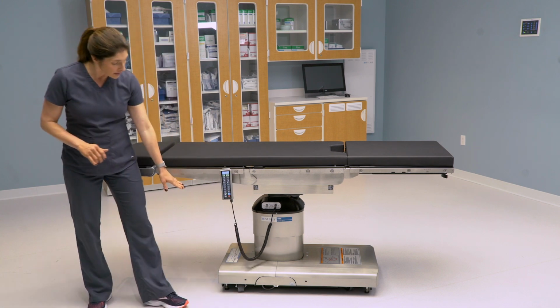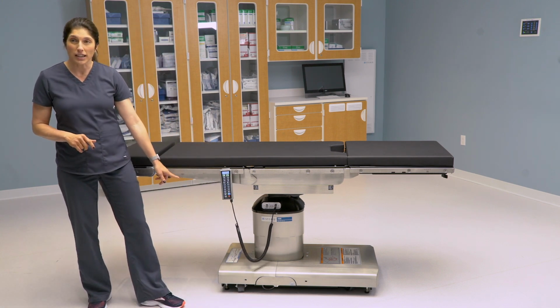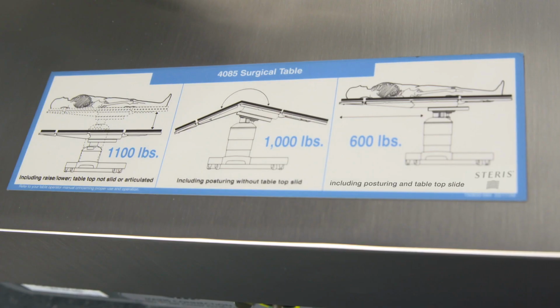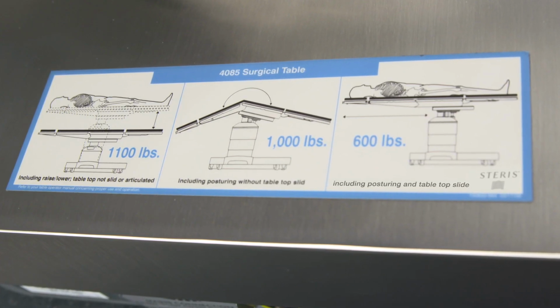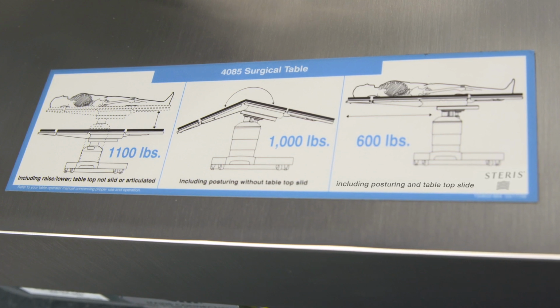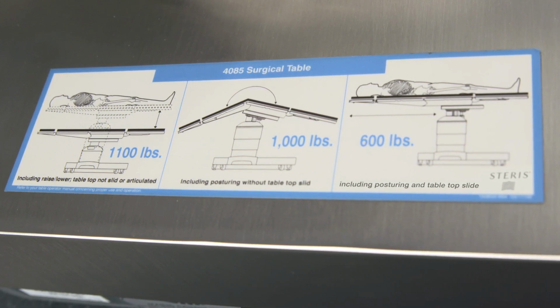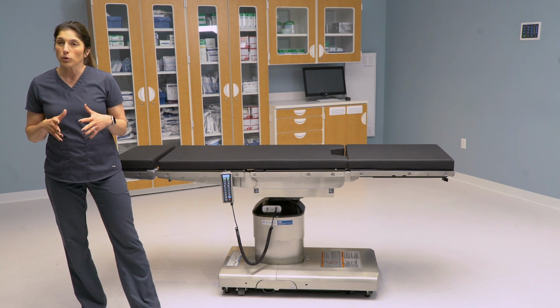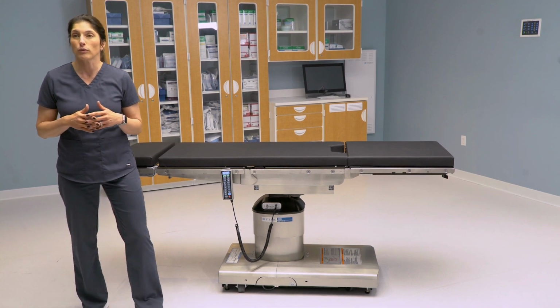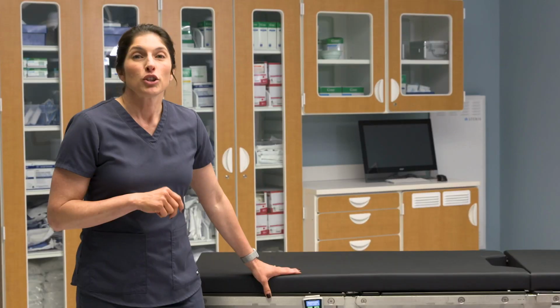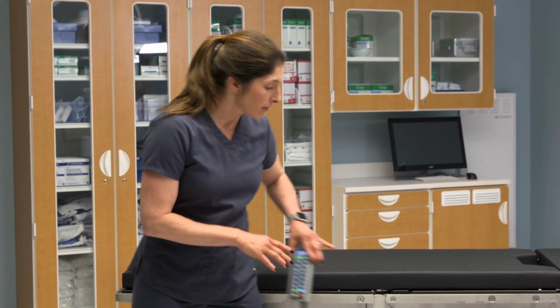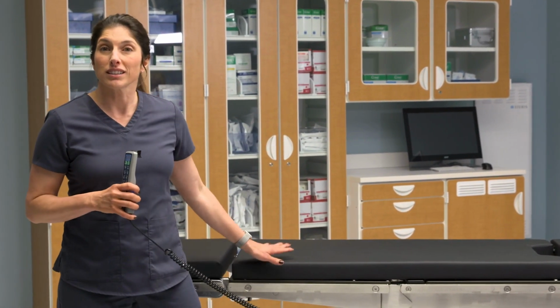At the anesthesia's head end of the base, you will notice there's a nice blue and white label that is the weight claim. I'm going to tell you what the weight claims are and how they differ from the 3085, but you don't have to memorize it because you can always look right down here to find out. So the 3085 in normal orientation held 1,000 pounds and in reverse orientation holds 500 pounds. The good news is no more reverse orientation. Well, there are actually two reasons why you would use reverse orientation on the 4085, but we'll go over that in a second. So now with the 4085 table, you have the ability to slide the tabletop.